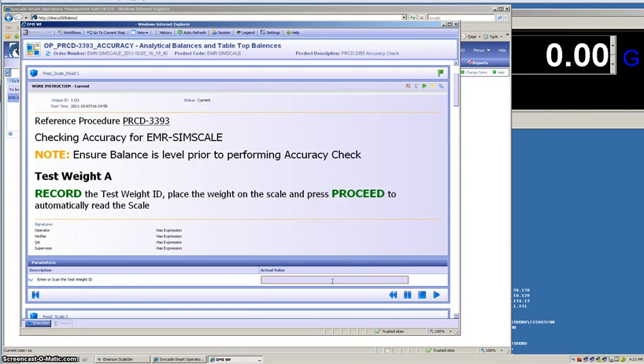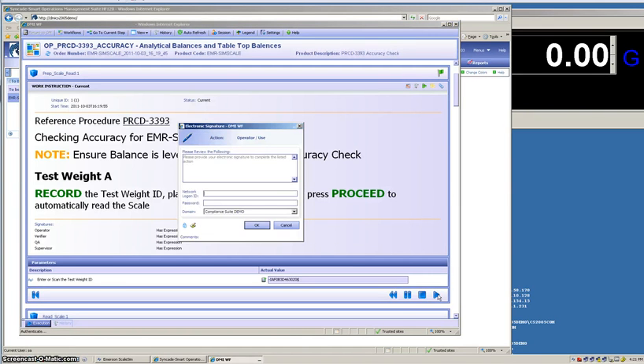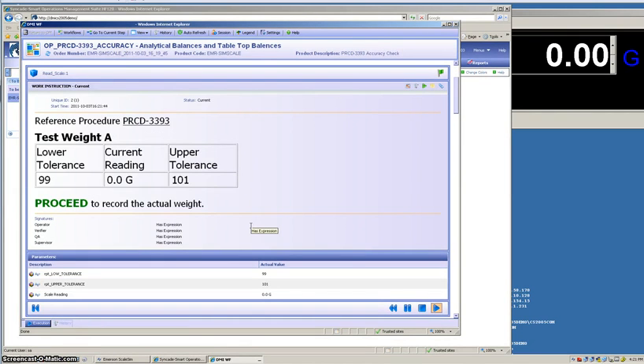So, with my barcode, I'm going to scan the ID of the test weight. Once the ID is recorded, I can proceed on. The Syncade system is designed to support Part 11 and capture electronic signatures as appropriate. With my signature captured, the system proceeds. Now, we have a current reading, and we're going to proceed again.